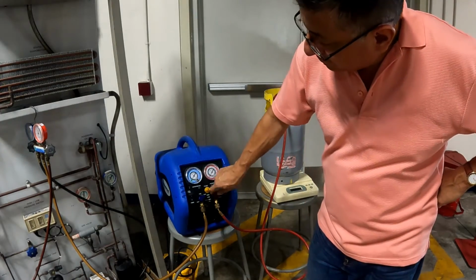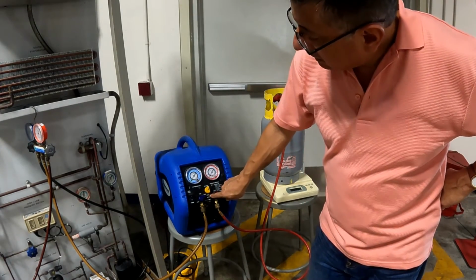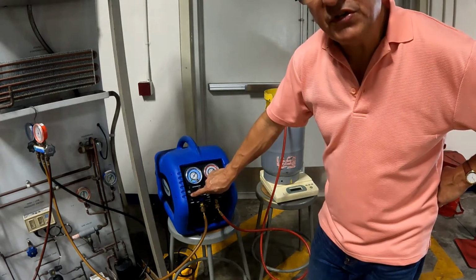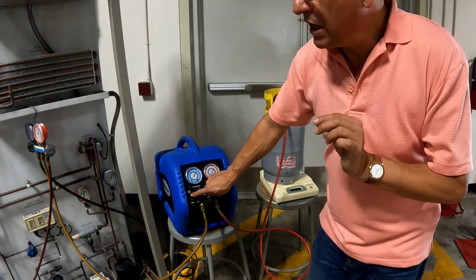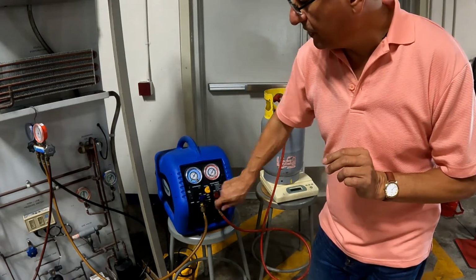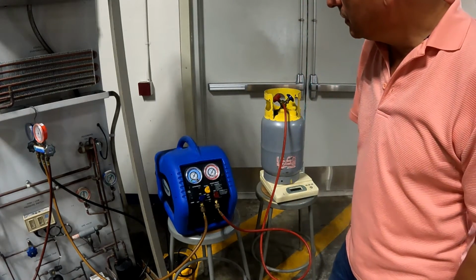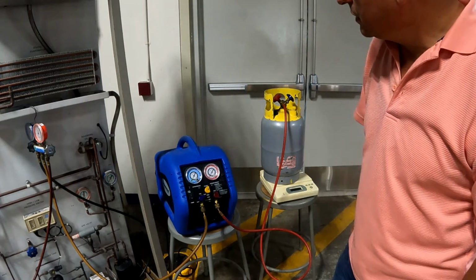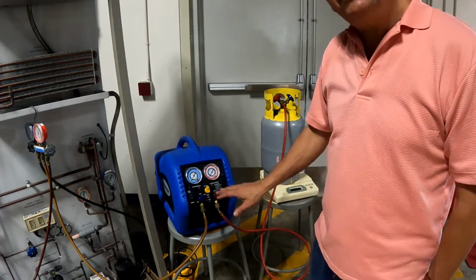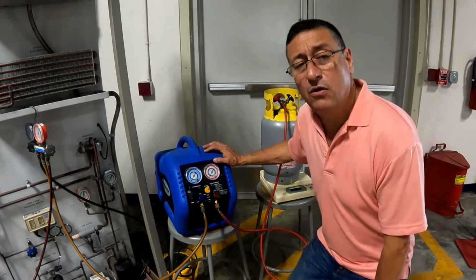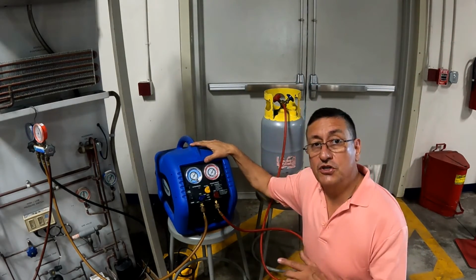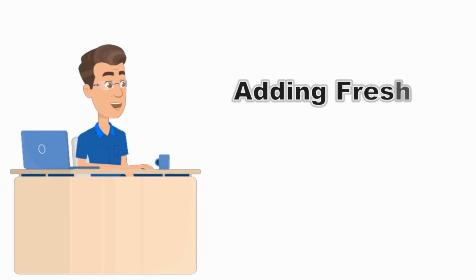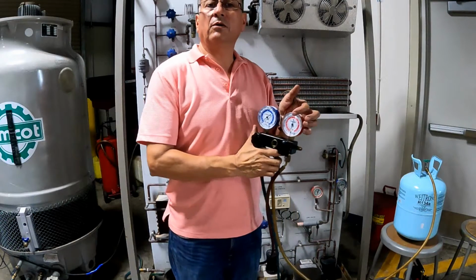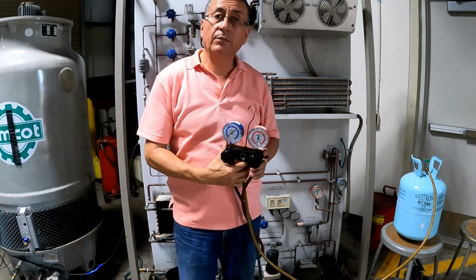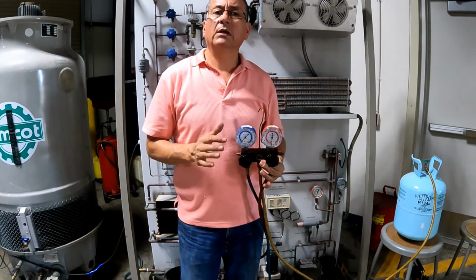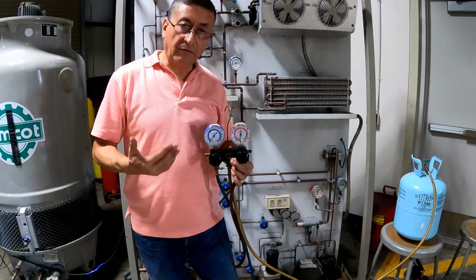Now we are going to select purge in the bottom, and we are going to purge the system in order to eliminate a small amount of refrigerant in both sides of the system. Okay, the system stopped by itself, and right now the system is ready to be recharged again. Now our system is empty. We do the vacuum. The system is ready to put the refrigerant back.